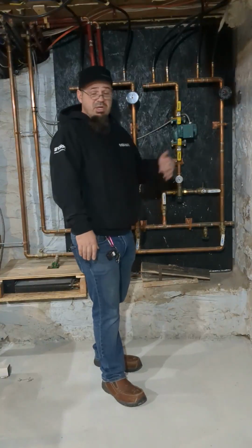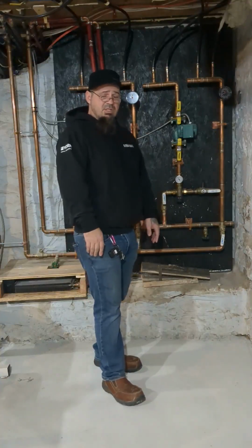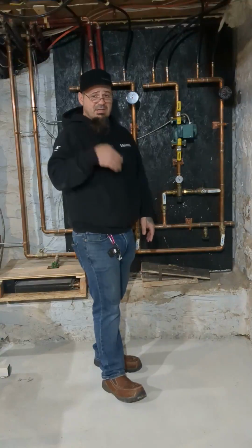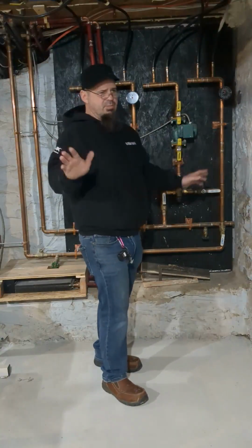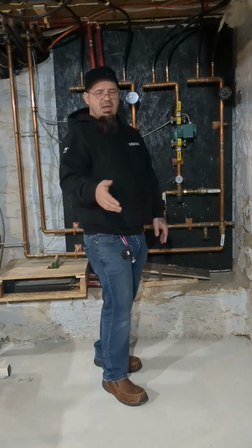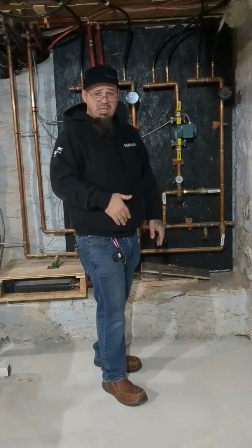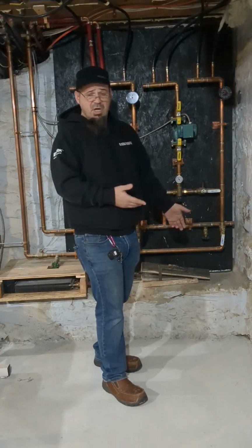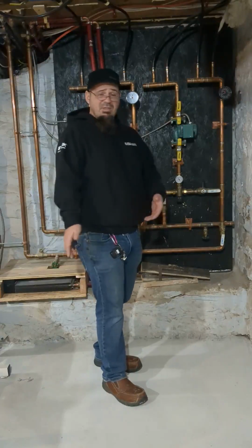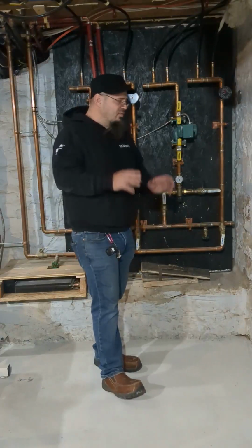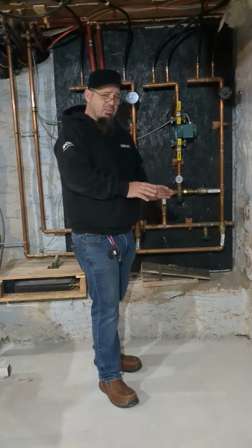I can tell you from experience, some of my systems, this one in particular, runs at about 126 degrees supply temperature. There are reasons for that I can and will explain in another video. Some people say you can't run temperatures that high. You can run temperatures that high depending on what type of system you have. I have systems that are buried in 6 inches of concrete that were done in the early 2000s. They run 140-degree water because if not, they don't even get hot.